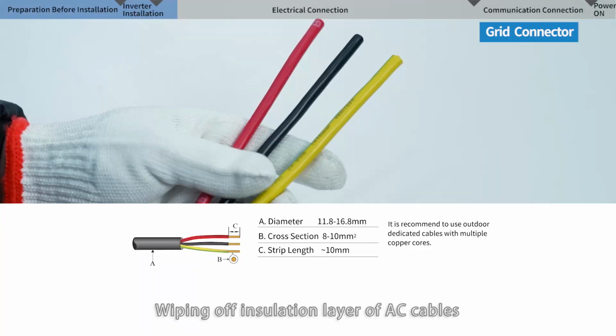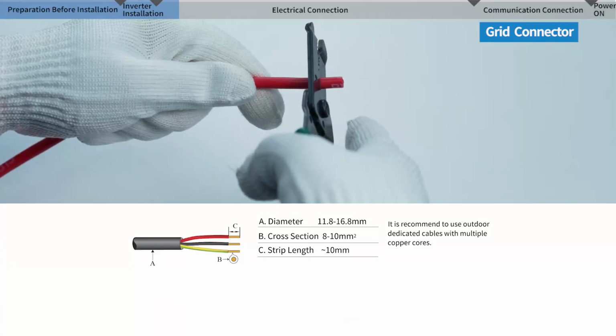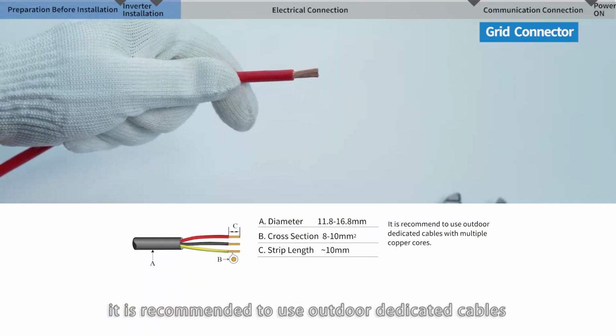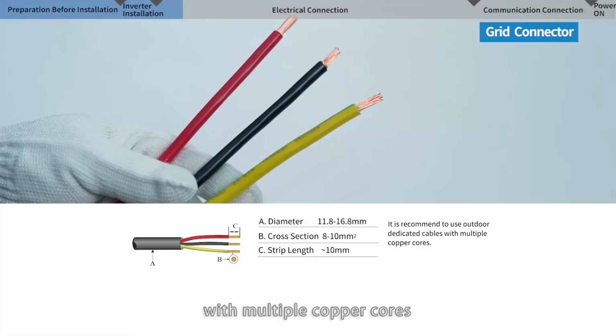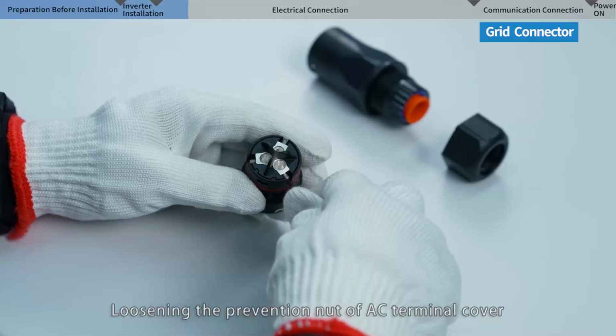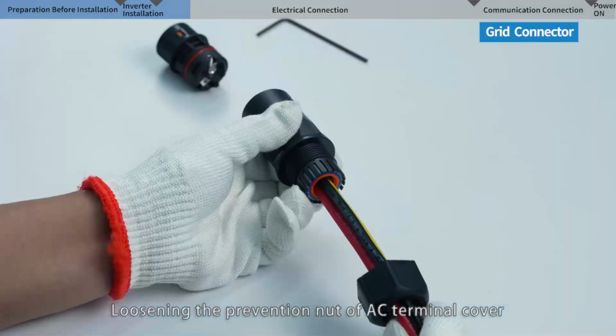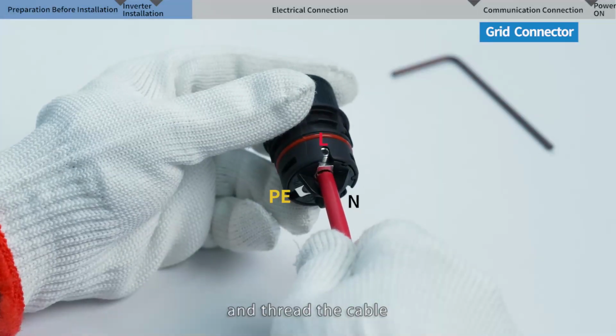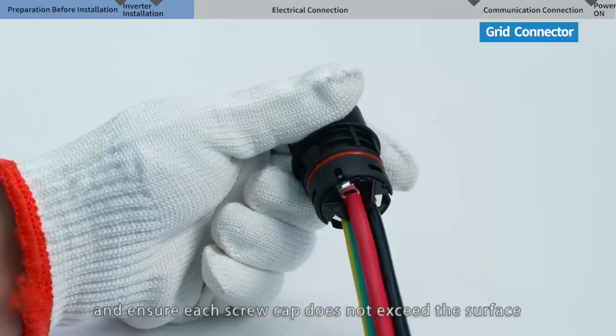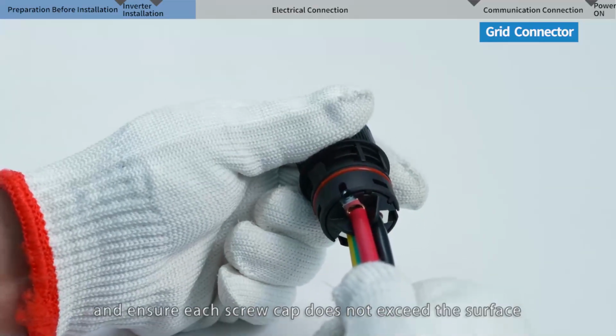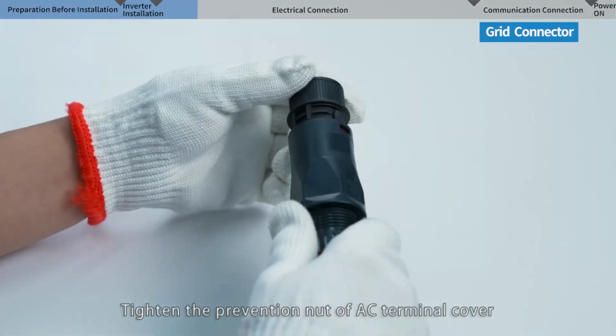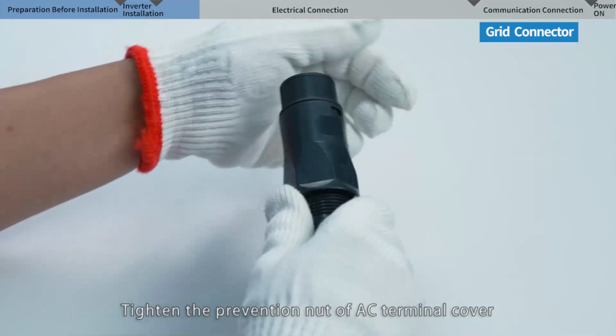Wipe off the insulation layer of the AC cables. It is recommended to use outdoor dedicated cables with multiple copper cores, cross-section 8 to 10 square millimeters. Loosen the prevention nut of the AC terminal cover and thread the cable. Tighten 3 screws to ensure each screw cap does not exceed the surface. Tighten the prevention nut of the AC terminal cover.